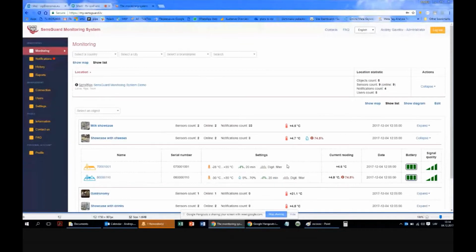Next setting is a digital filter. This is again connected to two ways how to measure temperature or humidity. For pharmacy, probably it is needed to measure spot temperature now, reading now. For some food storage, some greenhouses, probably we need to measure average temperature of product, and we develop digital filter that calculates some more readings to show the temperature.